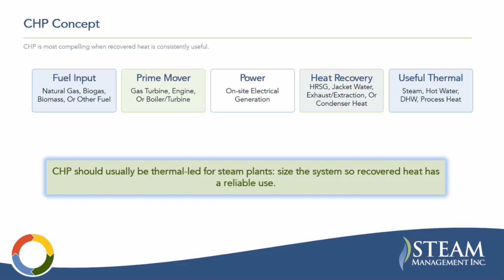I think I saw a comment. Are industrial processes ever reviewed to determine if the highest pressure steam is even required? For example, a plant outputs 250 psi, but a close review reveals that they could run at 200 psi and still service the max loads. Yeah, that's a great point.